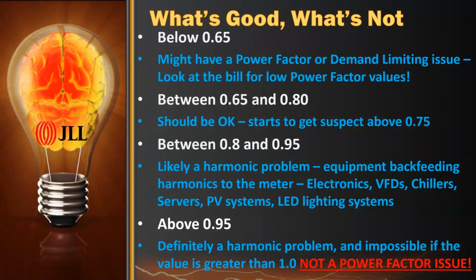And why it's a problem is that you're feeding electricity into the building, and there's equipment in the building that is producing a transient or a harmonic piece of energy, and that is acting like a broadcaster inside the building. The theory used to be, because there was so little of it in the building, and when I say used to be, I'm talking back when Elvis was around, that harmonic energy would get dissipated inside the building.